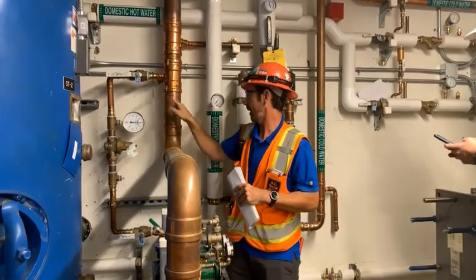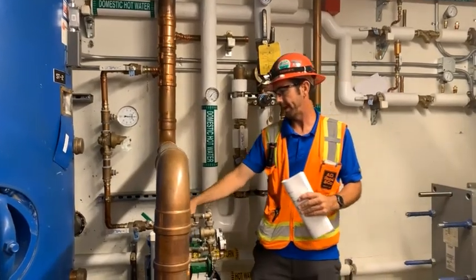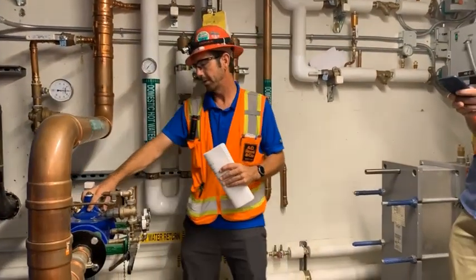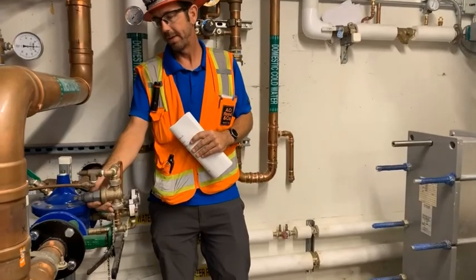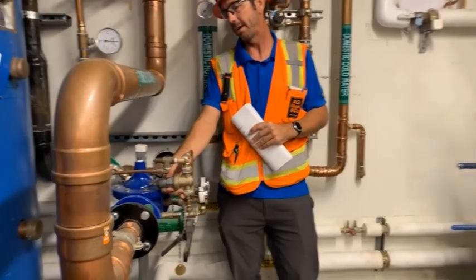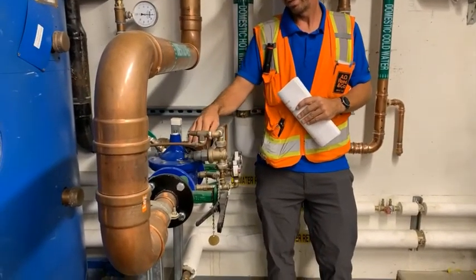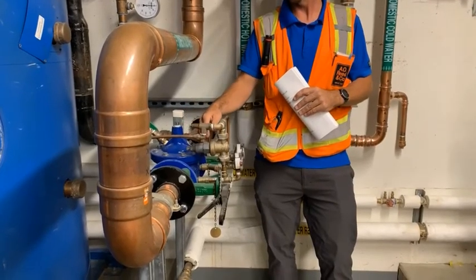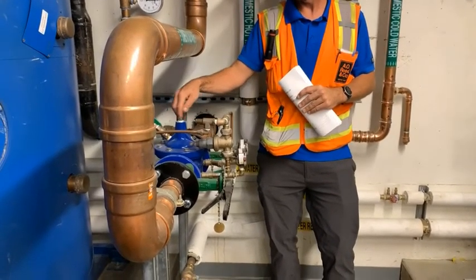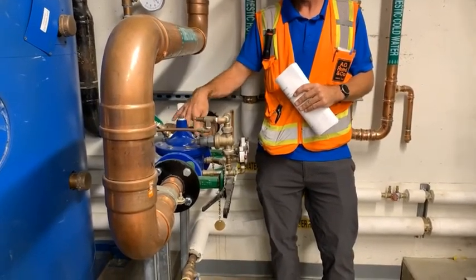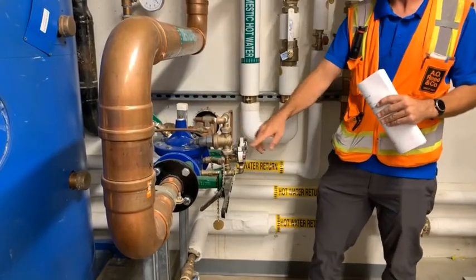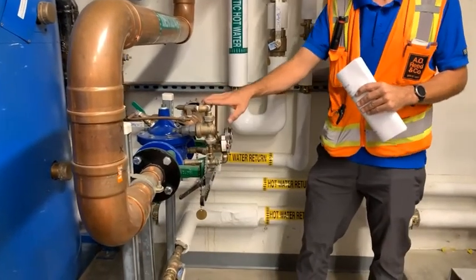So low flow here, high flow continues through the main valve down here. This one uses a pilot. So this valve right here is your pilot adjustment valve. This senses the downstream pressure and then opens and closes a main diaphragm valve up here. We have in and out gauges, in and out shutoff valves on this regulator.